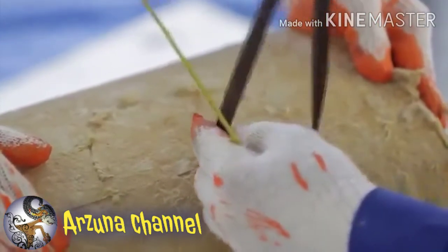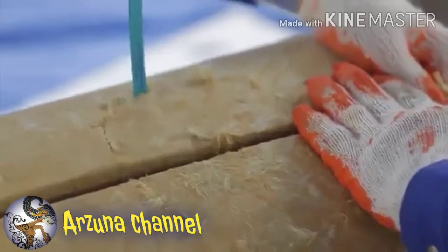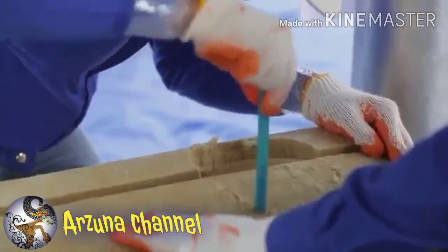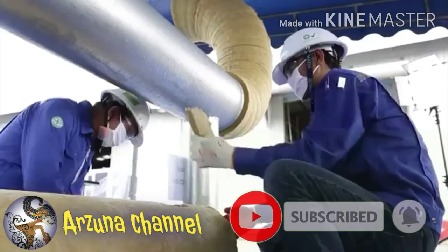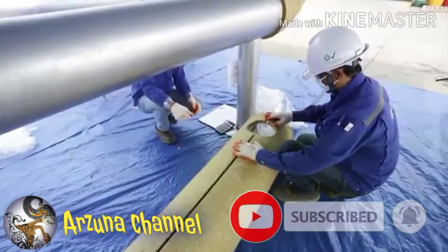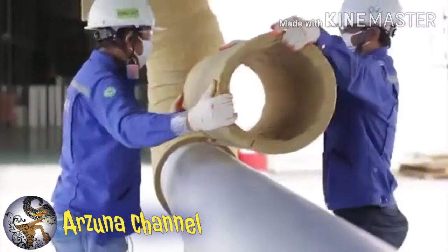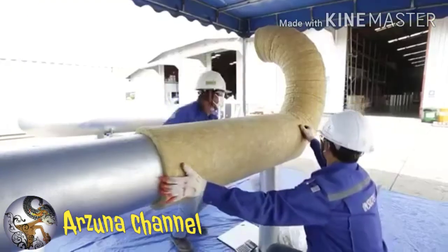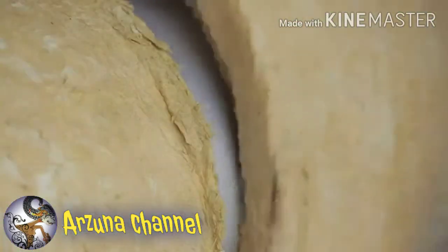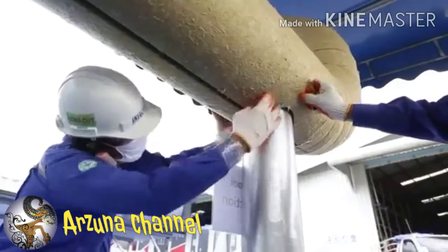With horizontal pipes, the lengthwise joint of the pipe section should be turned towards the underside at the 6 o'clock position. For vertical pipes, the lengthwise joints should be staggered at an angle of 30 degrees to one another. While the pipe support section needs to be insulated, Rockwool insulation has to be fabricated according to the size of the pipe support in order to ensure that the insulation is not damaged if the piping expands.